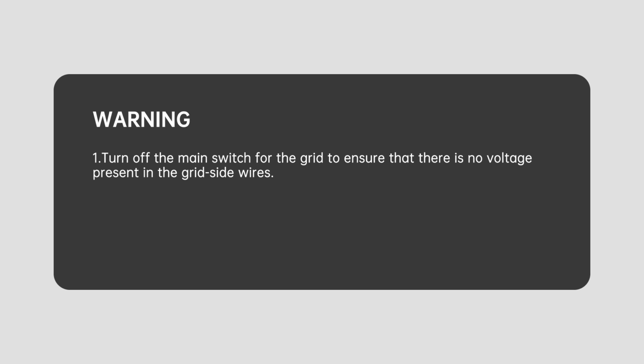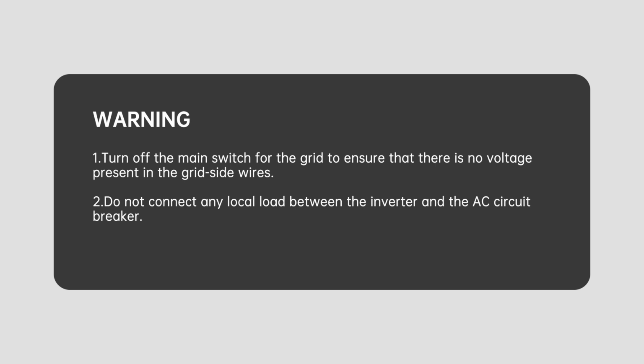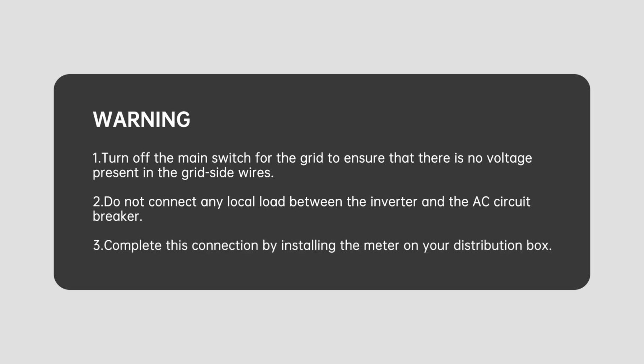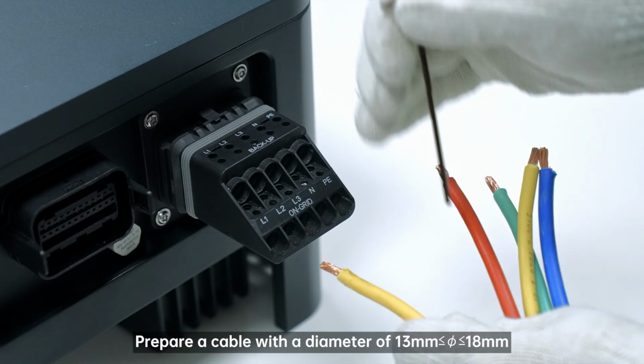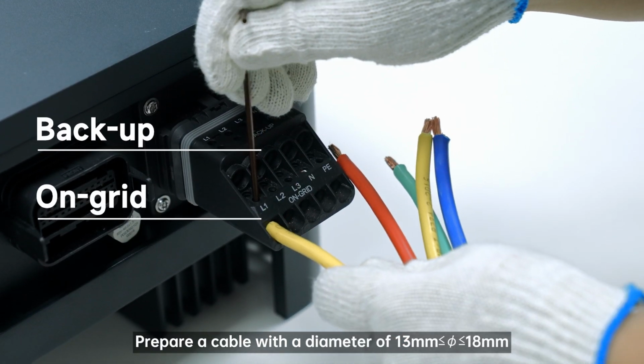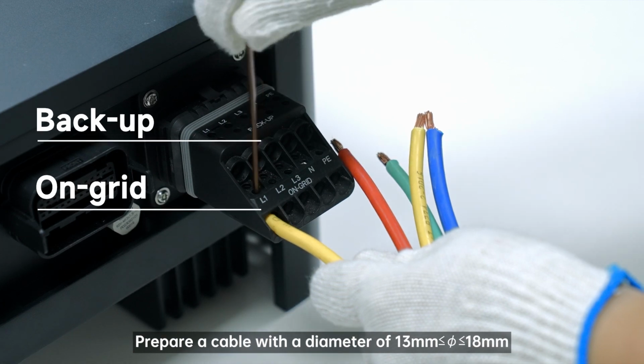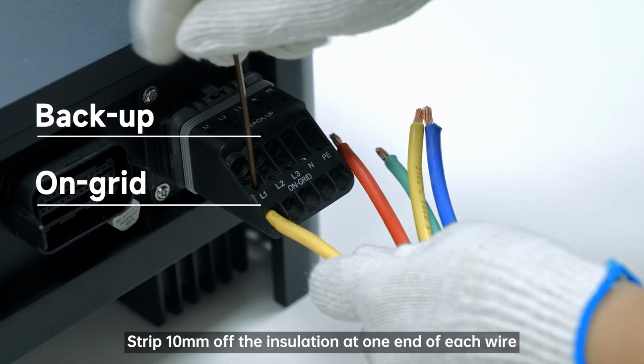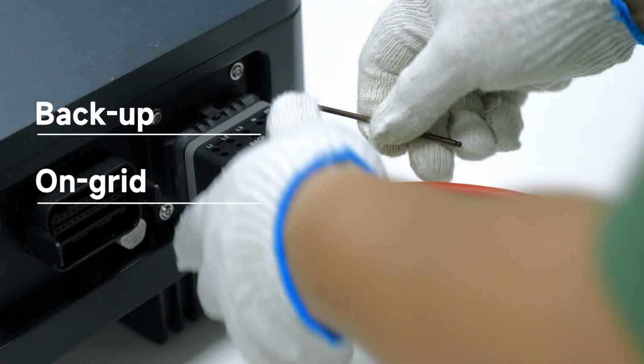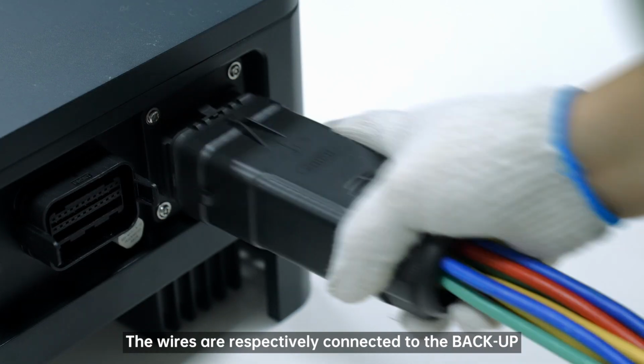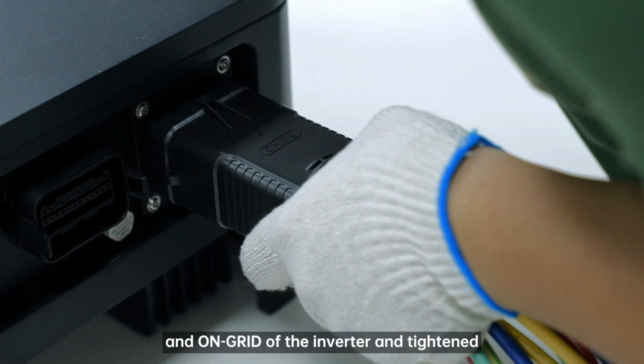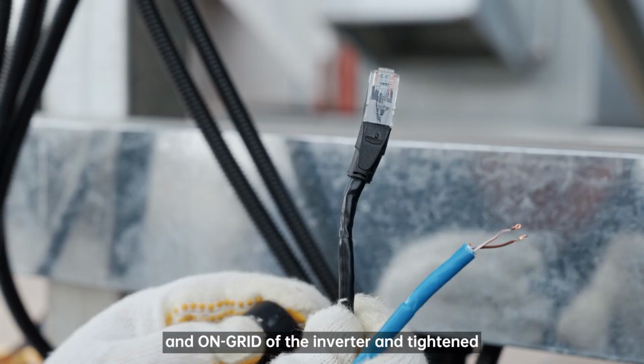Turn off the main switch for the grid to ensure that there is no voltage present in the grid side wires. Do not connect any local load between the inverter and the AC circuit breaker. You should complete this connection by installing the meter on your distribution box. Prepare a cable with a diameter of 13 to 18 millimeters. Strip 10 mm off the insulation at one end of each wire. The wires are respectively connected to the backup and on-grid of the inverter and tightened.